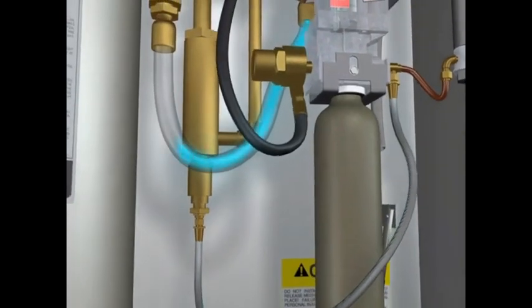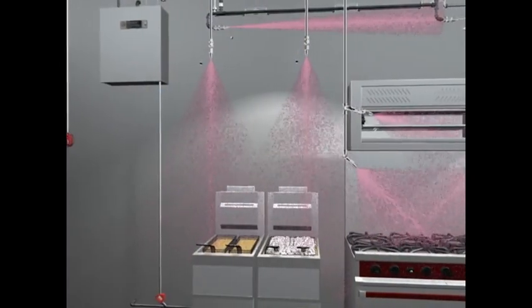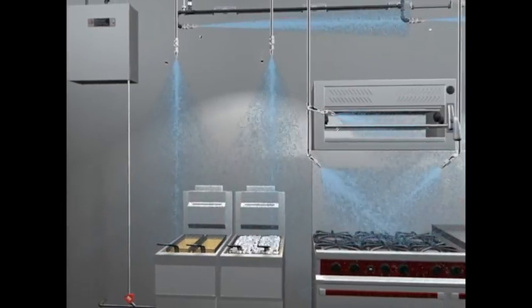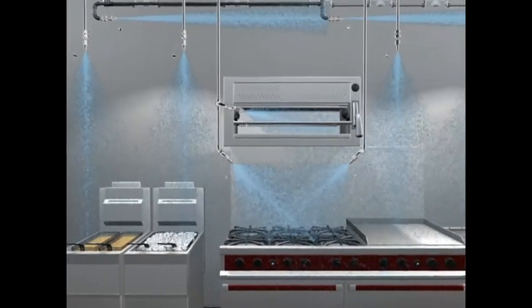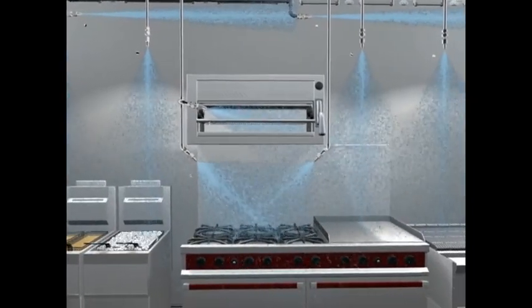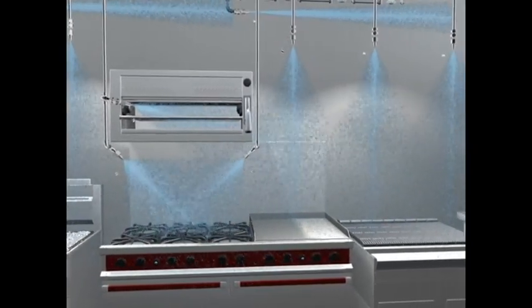Almost immediately, the Piranha system initiates phase two of protection and begins to discharge water, cooling the area and the remaining fuel below the stage at which it can reignite. This takes about one minute, approximately fifteen times faster than conventional wet chemical systems.